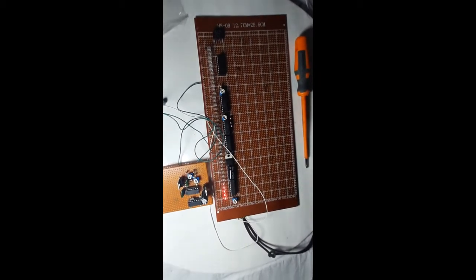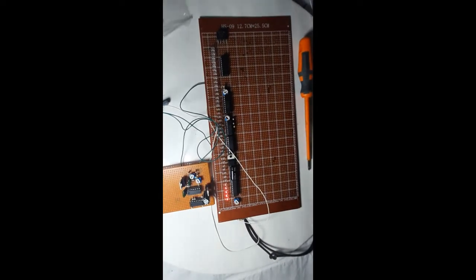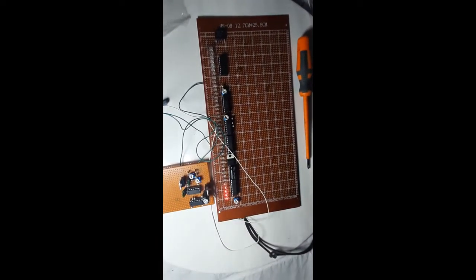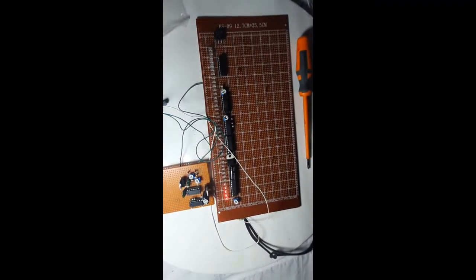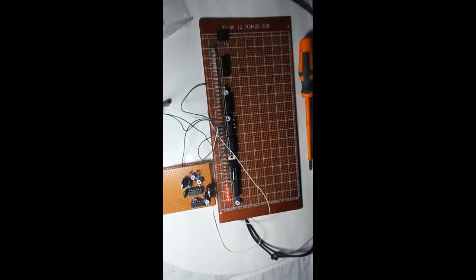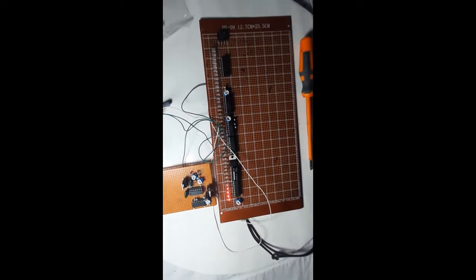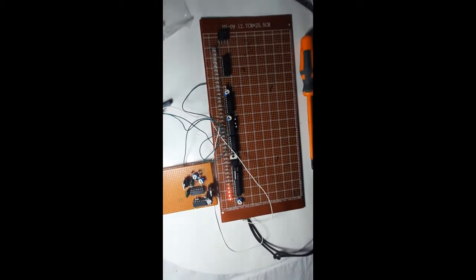And when we make the graph, we find an error. The error is displayed here very clearly. The boiler water level is at the minus 10 of the gauge glass, but here it is showing, say, minus 9 or so.